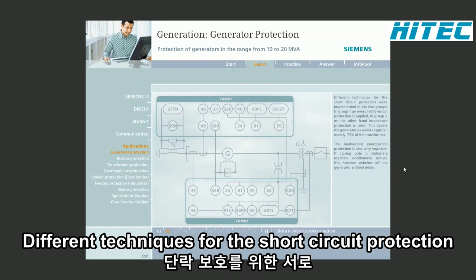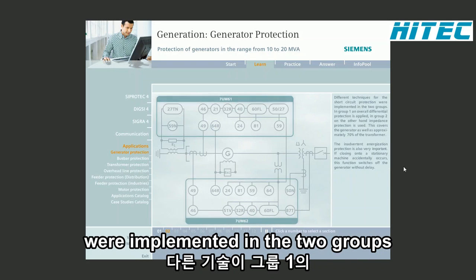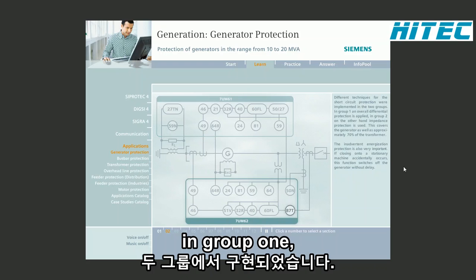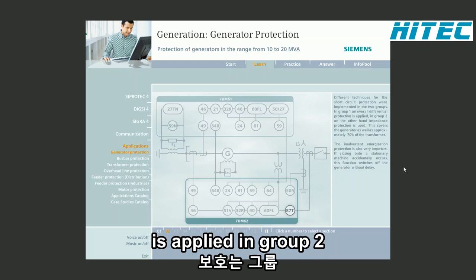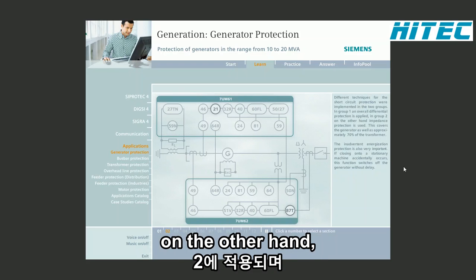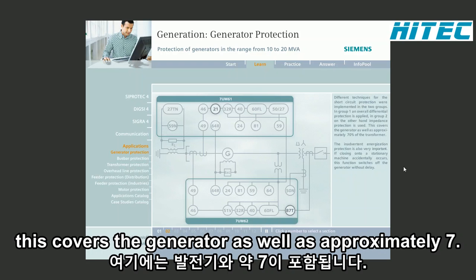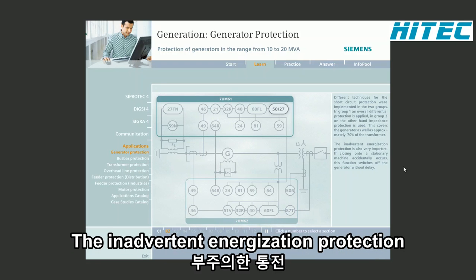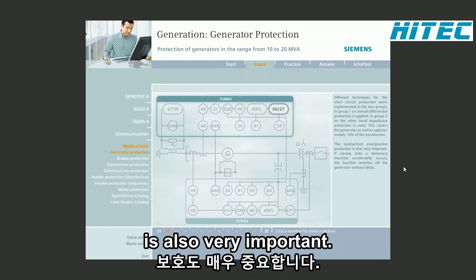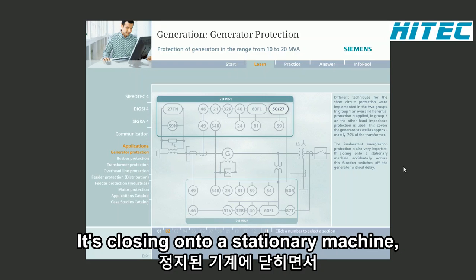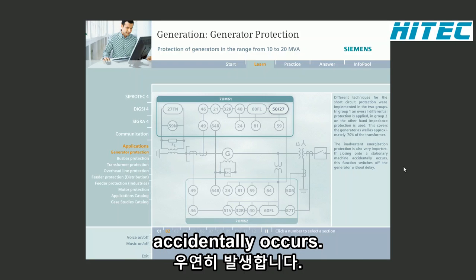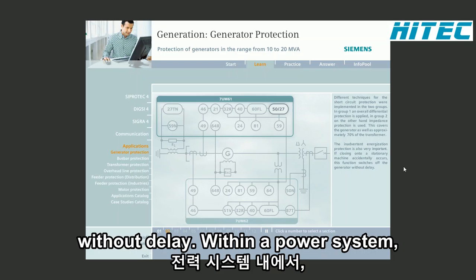Different techniques for the short circuit protection were implemented in the two groups. In Group 1, an overall differential protection is applied. In Group 2, on the other hand, impedance protection is used. This covers the generator as well as approximately 70% of the transformer. The inadvertent energization protection is also very important. If closing onto a stationary machine accidentally occurs, this function switches off the generator without delay.